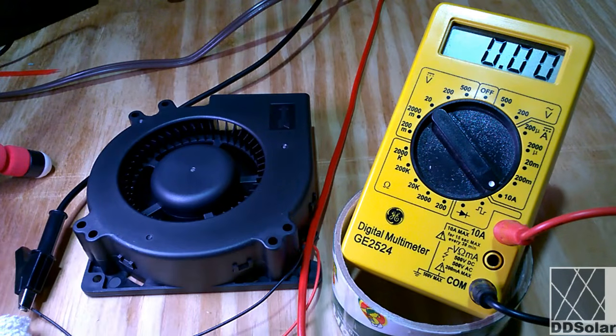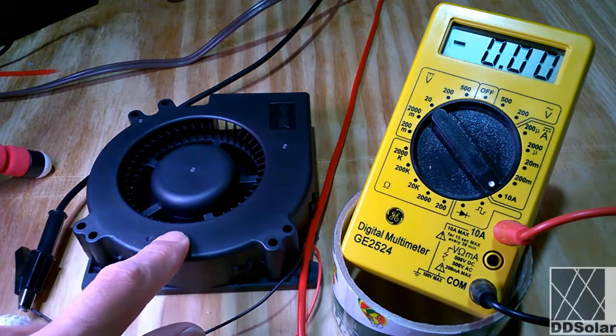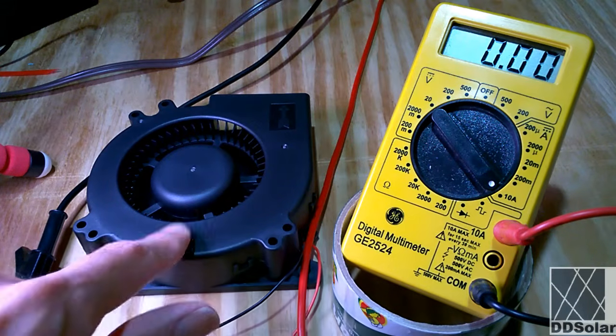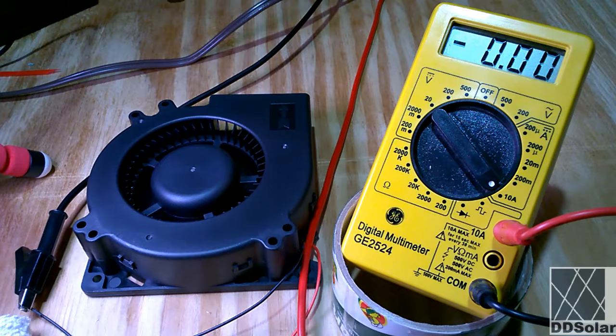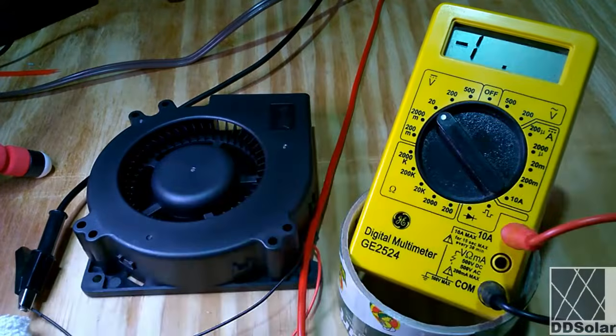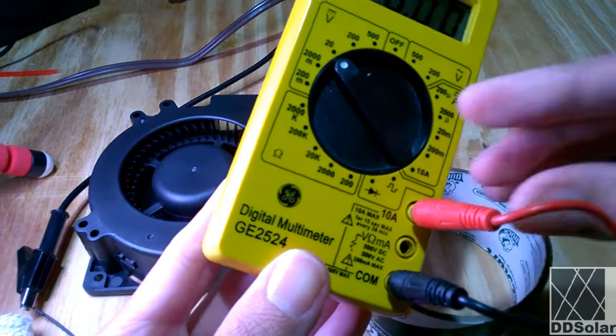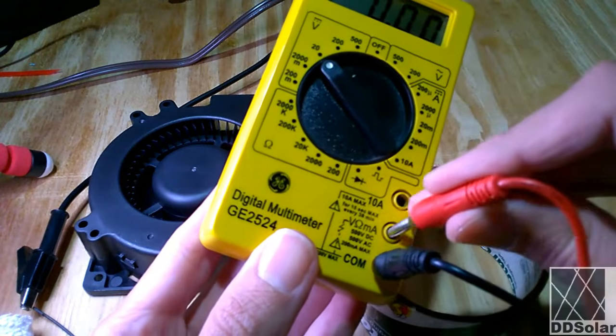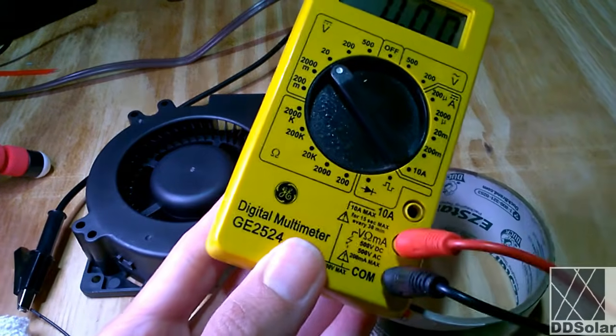What if I want to know the voltage coming out of the power supply into the fan while the fan is operating? Obviously, when the fan turns on, the reading could change. And here's where a number one mistake is often made. You switch the dial straight to 20 volts, and you start taking the measurement. The problem is your meter is now in a short circuit. So I've got to remember to always unplug this connection here and put it back where it belongs so I can take a voltage measurement. And if I don't, I can burn out the meter.